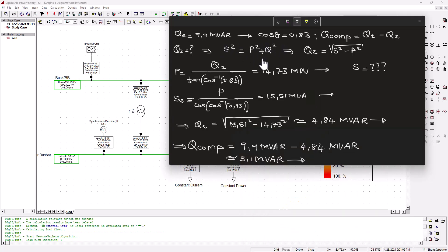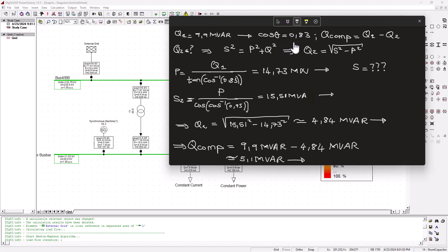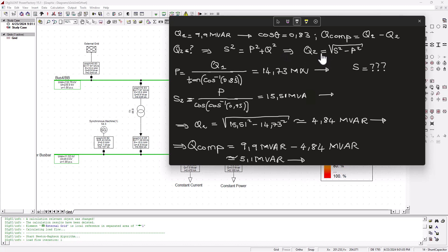To save us some time, I went ahead and did some calculations, so let's quickly go through it. We know that Q1 is the actual reactive power that the grid is supplying into the system, and that is at this power factor. So we need to find the compensation here, and that is calculated by doing Q1 minus Q2. But what is Q2? That's what we are looking for. Using the power triangle, S squared equals P squared plus Q squared, and that means Q is the square root of S squared minus P squared.